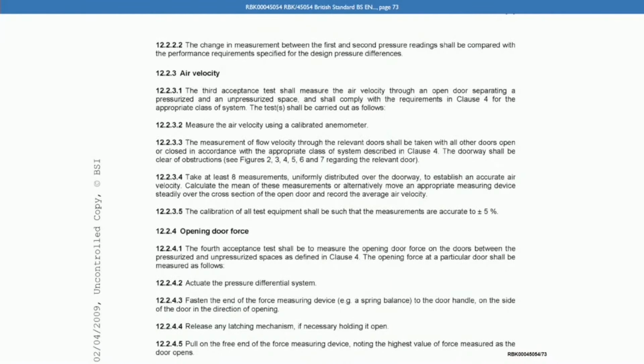Were you aware that the test, if we go back to page 73, this door velocity airflow test, if you look at 12.2.3.4, do you see there it says that you have to take at least 8 measurements uniformly distributed over the doorway to establish an accurate air velocity? Calculate the mean of these measurements, or alternatively move an appropriate measuring device steadily over the cross-section of the open door and record the average air velocity. Now, did you do that?